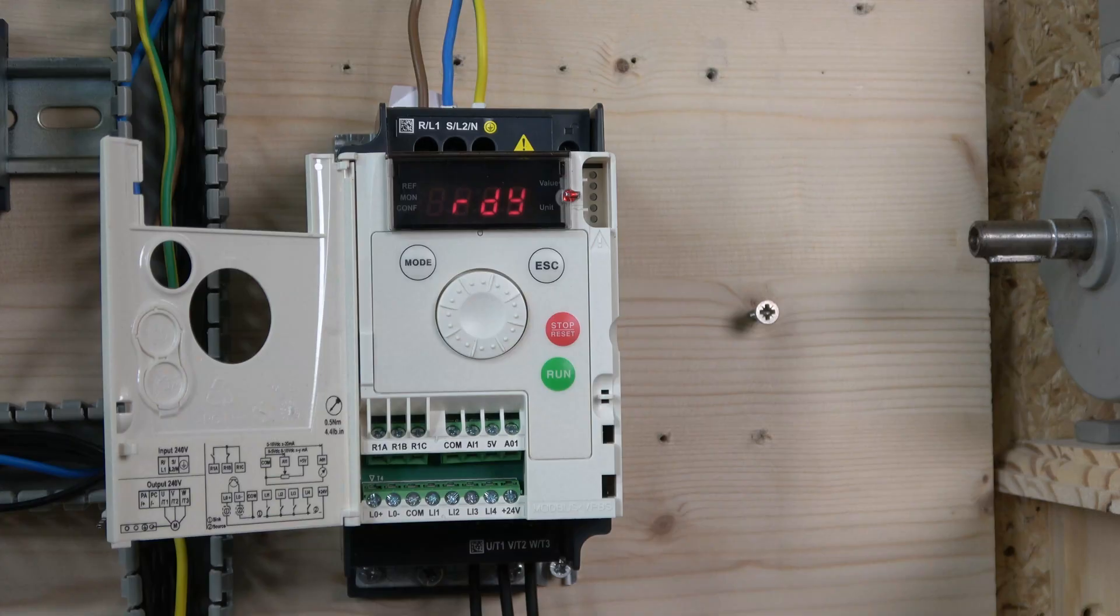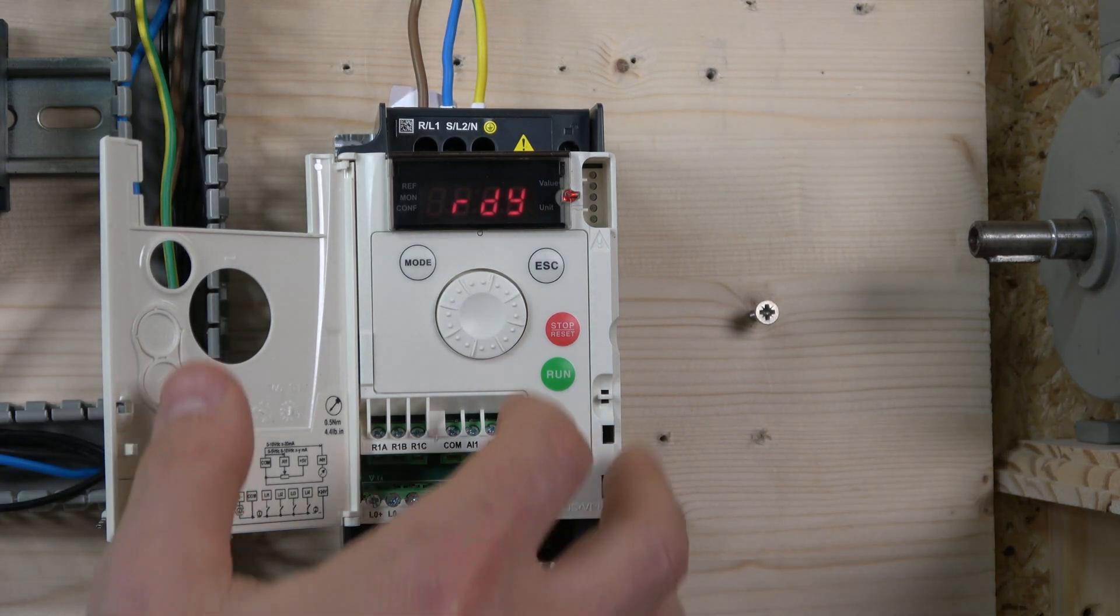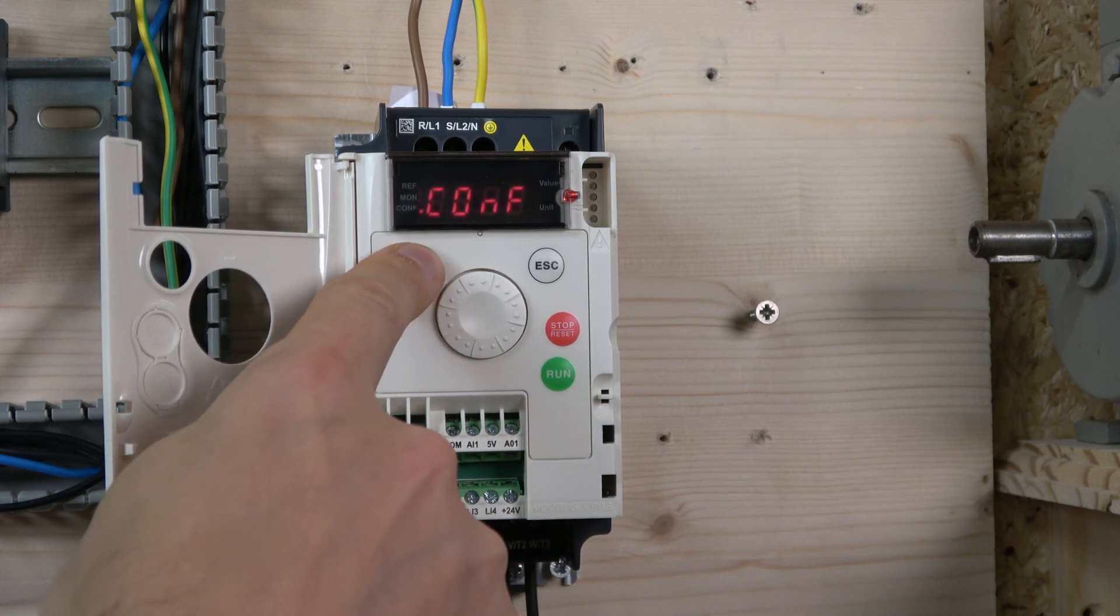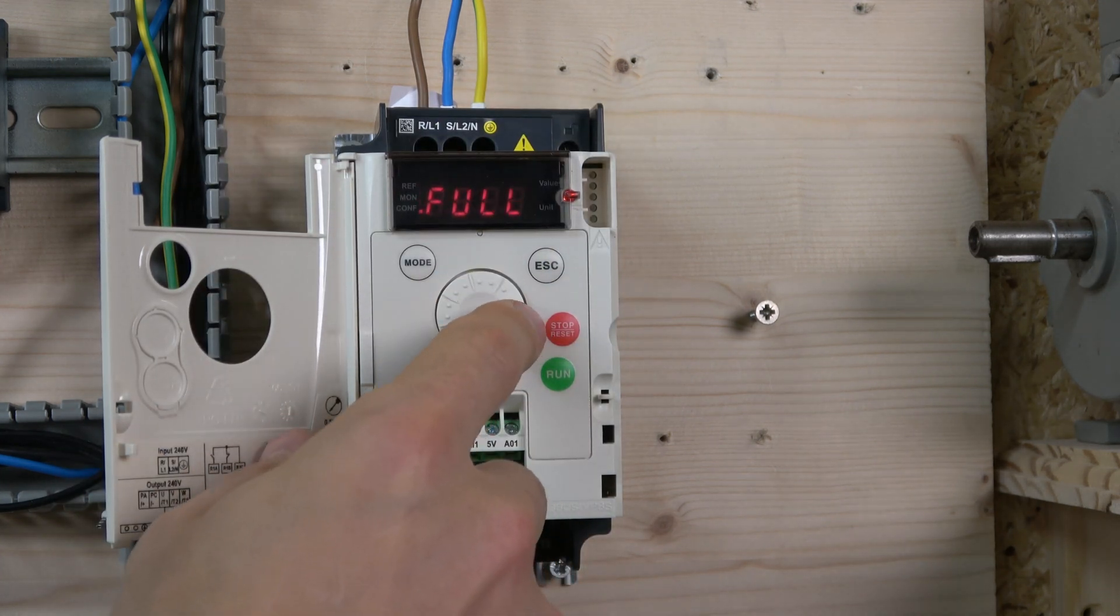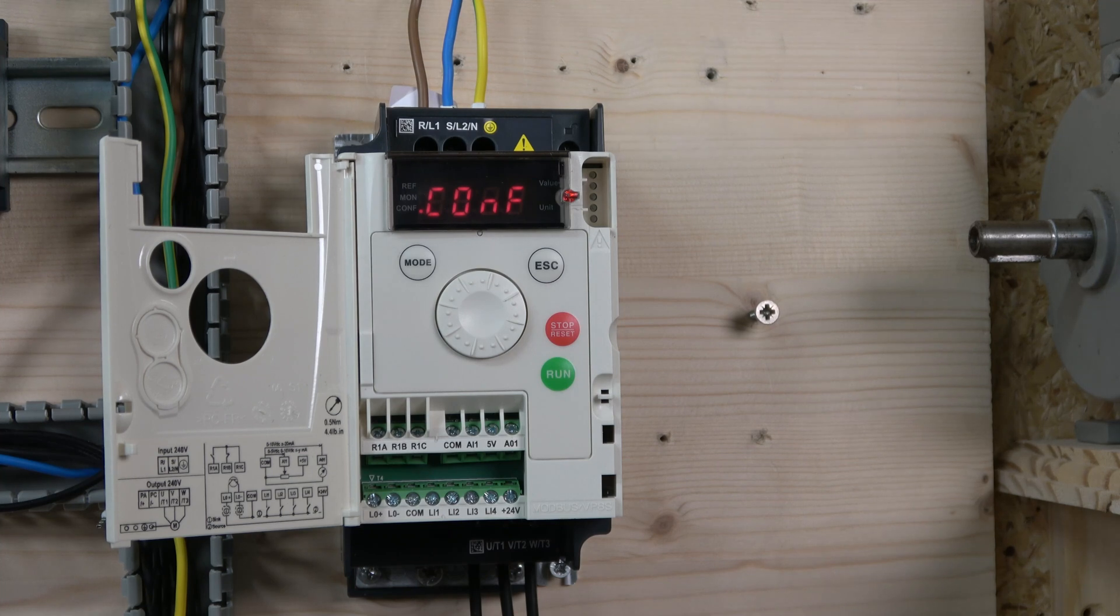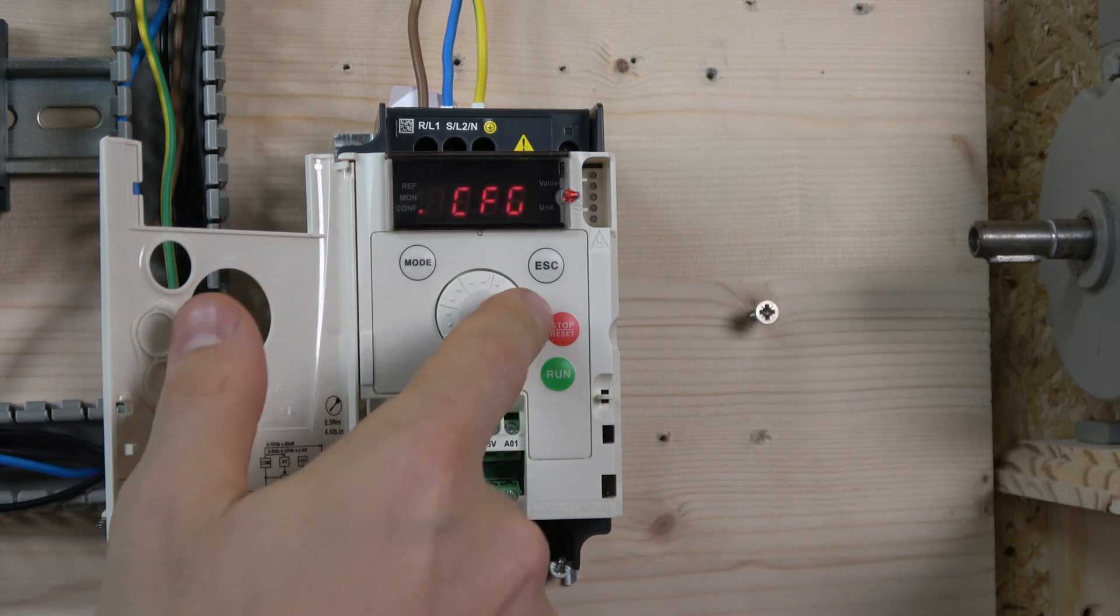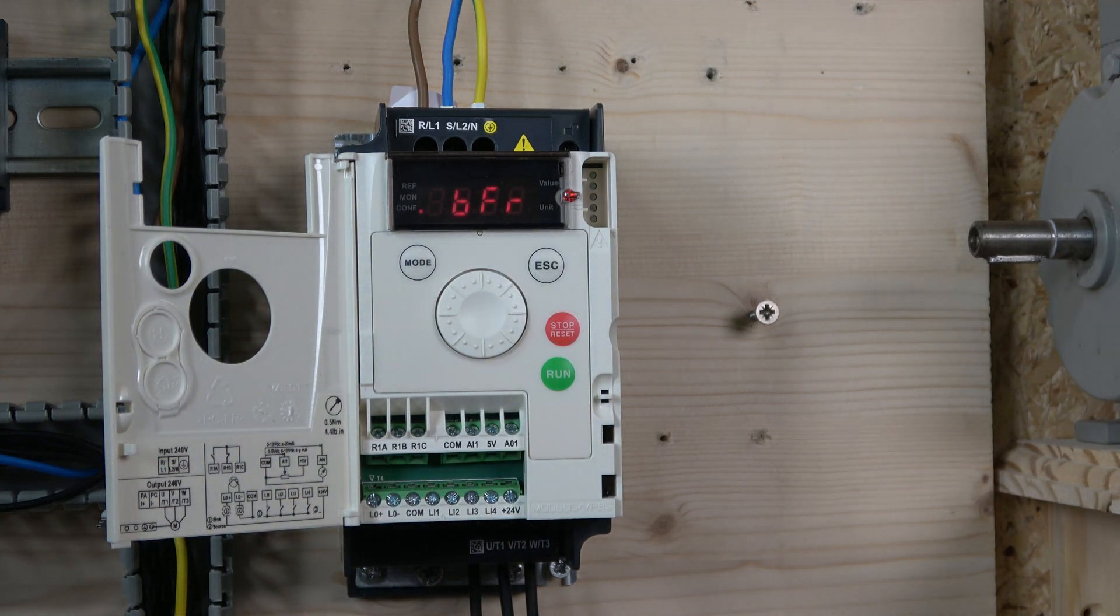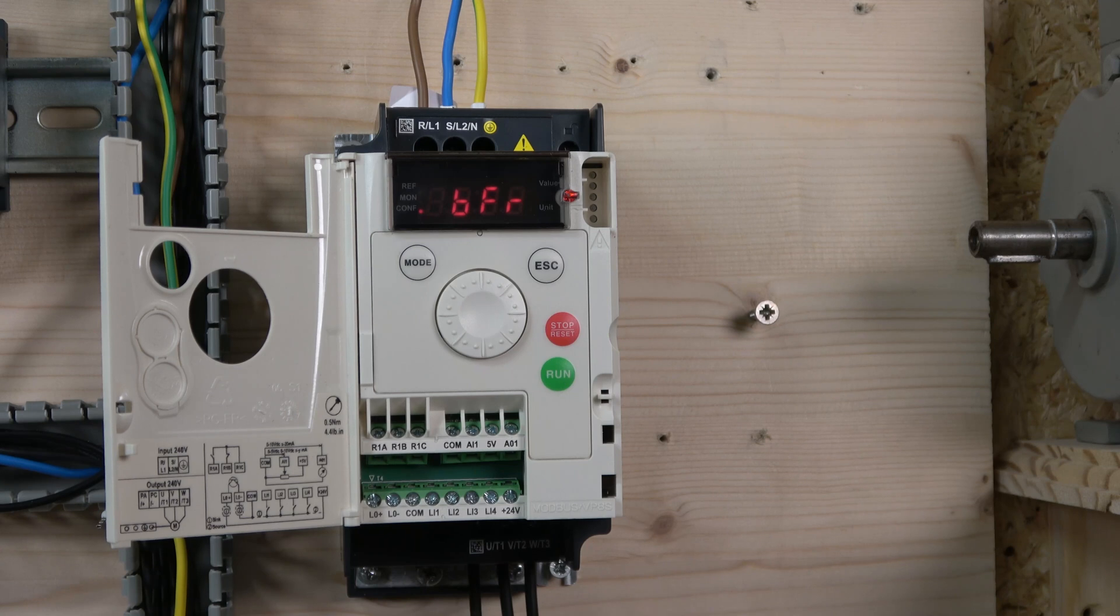For drive commissioning, we need to go to menu DRC. The mode button flips through menus, which the dial can also do. Go to configs, then full, then to parameter group DRC where all the motor parameters are. The first one is motor rated standard frequency, which in our case is 50 Hertz - that's already there.